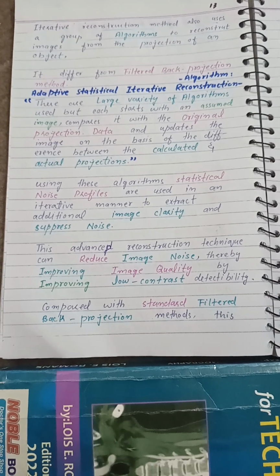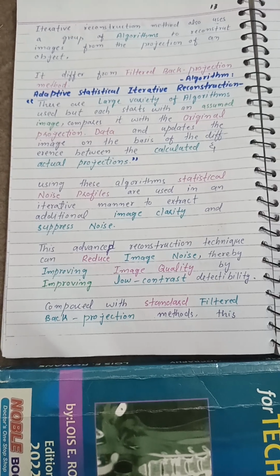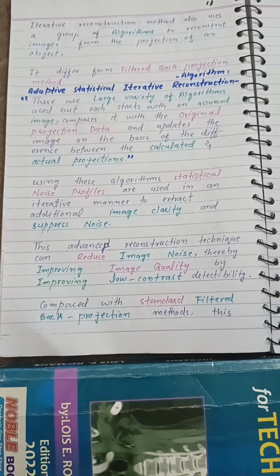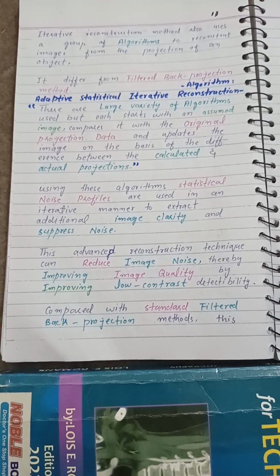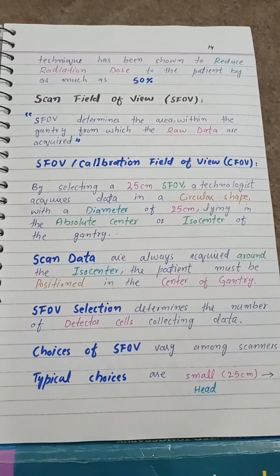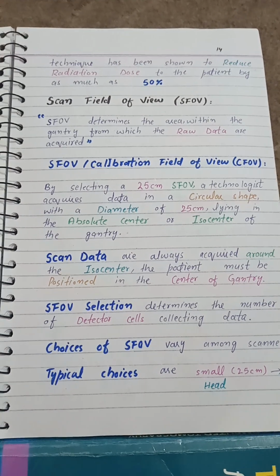This advanced reconstruction technique can reduce image noise, thereby improving image quality by improving low contrast detectability. Compared with the standard filtered back projection method, this technique has been shown to reduce radiation dose to the patient by as much as 50%.